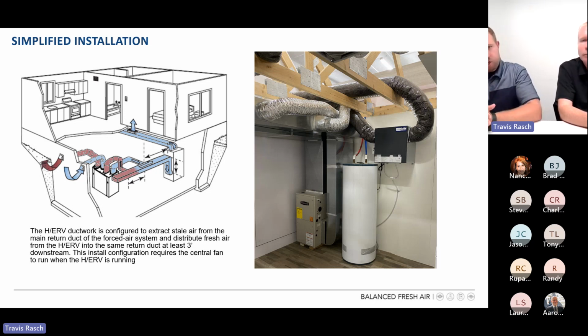In the picture shown here, we're going to the return side of the air handling system. We want some separation between the two, and this requires that the central fan of the air handler be running. Otherwise, the HRV or ERV would just be recycling air inside that return duct, so there's some interaction required between the air handler fan and the HRV or ERV.